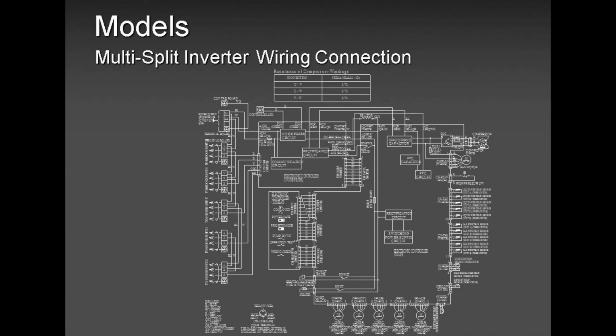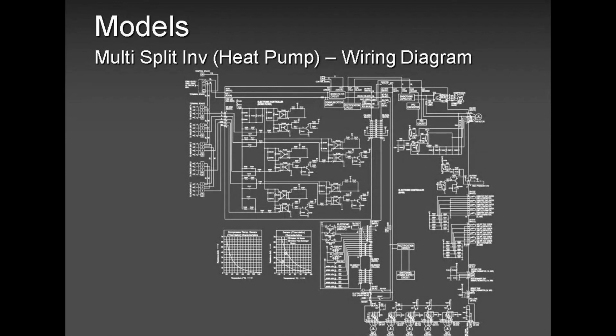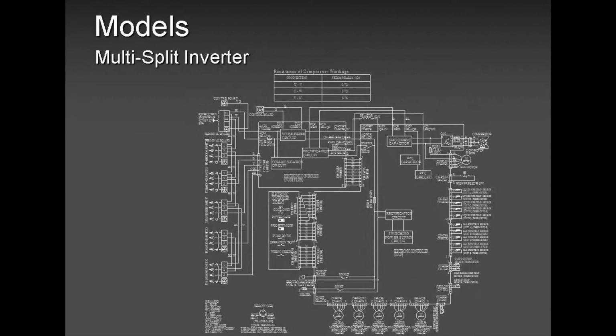Those are your sensors. Compressor discharge temperature sensor. That sensor sometimes goes bad, but in most cases, when you measure the sensor, it's not bad. It's good. Why? Because it's low on refrigerant. The system has sensed that there is low refrigerant, so the compressor is overheating. That's how you get high discharge. So please remember, these sensors, in all my 6 years, very rarely go bad. Very, very rare. In most cases, it's to do with refrigerant, either low, high, or less.